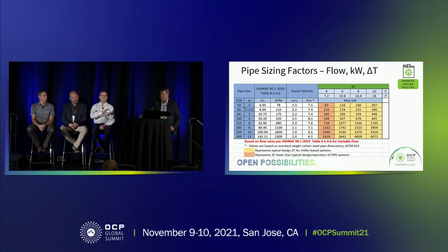When we look at a lot of retrofit applications, right? We're not talking greenfield construction purpose-built, we're talking retrofit applications. A lot of existing facilities that are out there are going to be looking at modifying systems that have chillers attached to them. And chiller systems are not going to be doing delta T's higher than 10 degrees centigrade without a CDU in place.